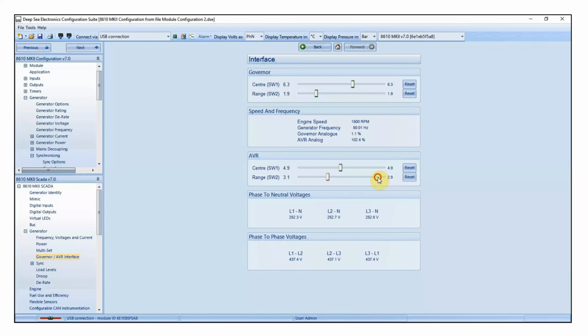You'll see from this example that we have very different switch 1 and switch 2 values for the governor and AVR. It honestly does not matter what switch 1 and switch 2 values you get. 0 and 3, 6 and 2, 10 and 1. Honestly, it does not matter, as long as you achieve what we're asking you to achieve, the switch positions don't matter. So you can see now that we've ended up with quite a high switch 2 value for the AVR. And finally, that AVR analog has started to decrease. We keep increasing that switch 2 value all the way until we get an AVR analog percentage of, again, 80%. Looking for somewhere between 75 and 85%.